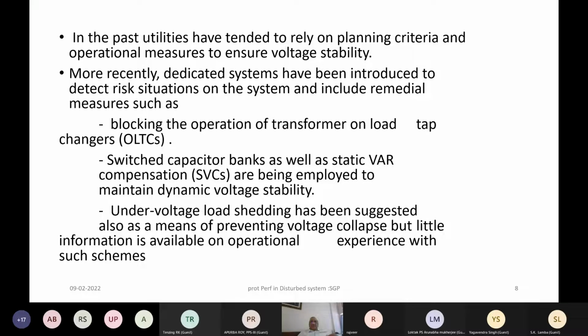Some of the actions which are required is blocking the operation of the transformer on-load tap changer. When the reactive power flow increases due to voltage drop, if the OLTC operates at this time to boost the voltage, actually it becomes counterproductive, because then more power will be drawn as you boost the voltage, and then again the power factor will be poor and it will further lead to the collapse. So on the load center side, when there is an overload situation on the transmission line, you should block the operation of the on-load tap changer of the load center side transformers.